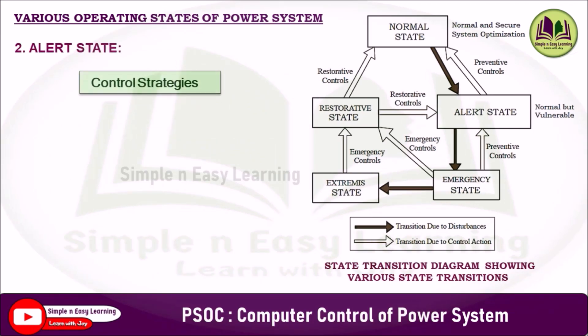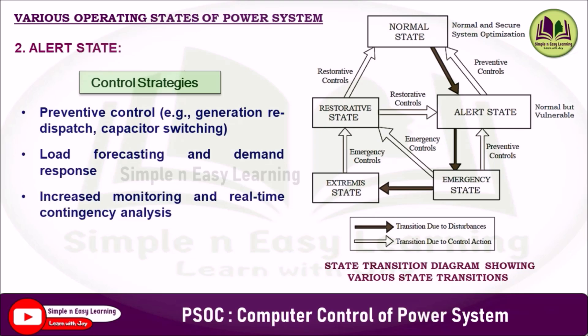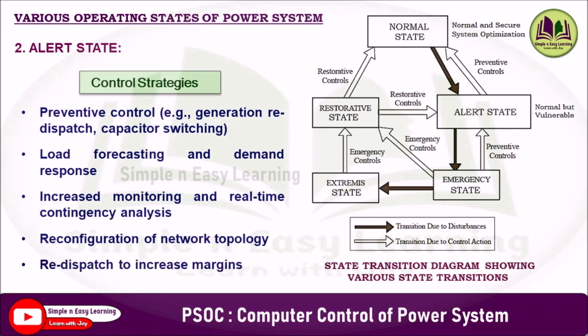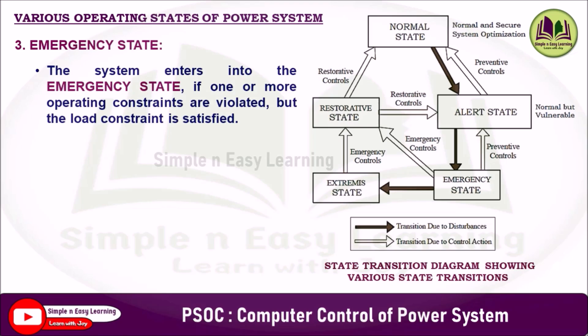Control strategies in the alert state include preventive control (for example, generation redispatch or capacitor switching to improve reactive power), load forecasting and demand response, increased monitoring and real-time contingency analysis, reconfiguration of network topology, and redispatch to increase margins.